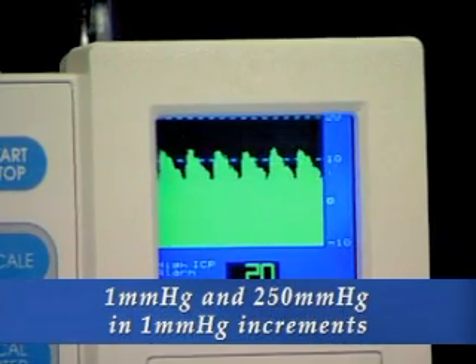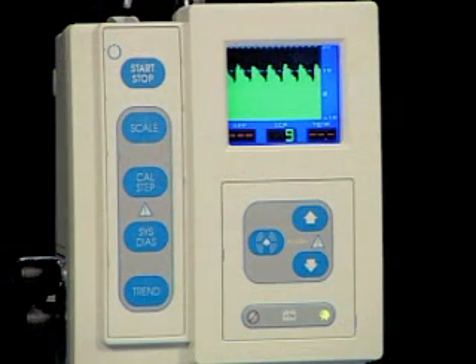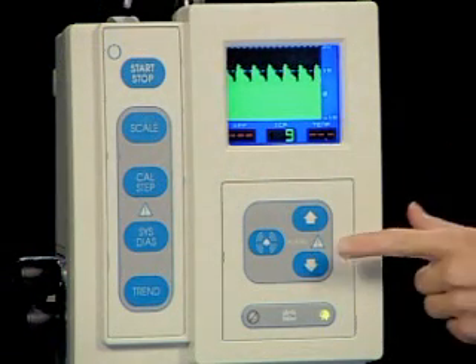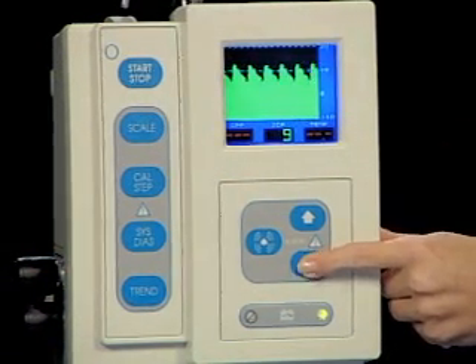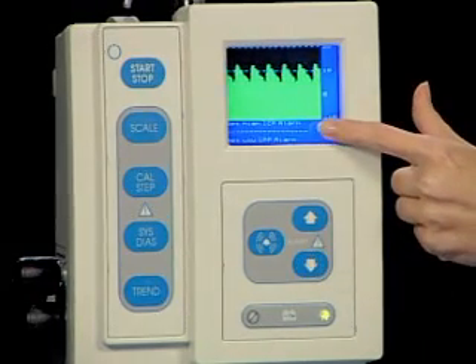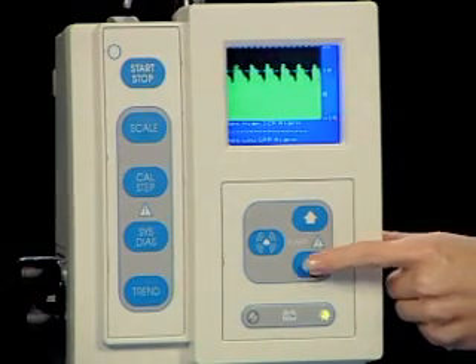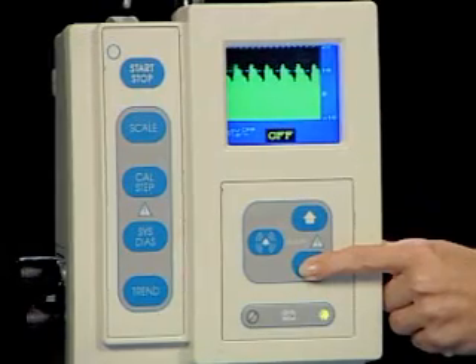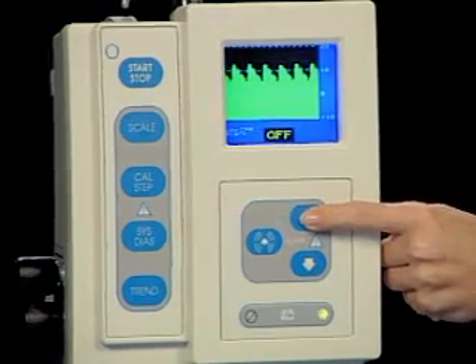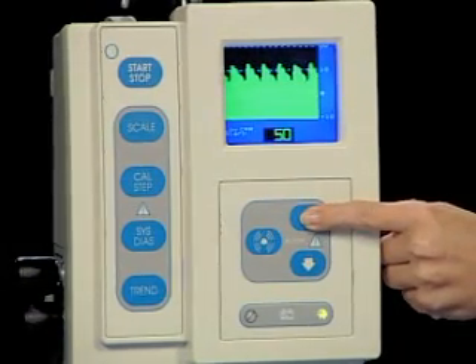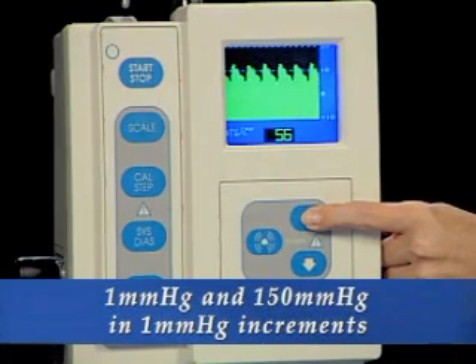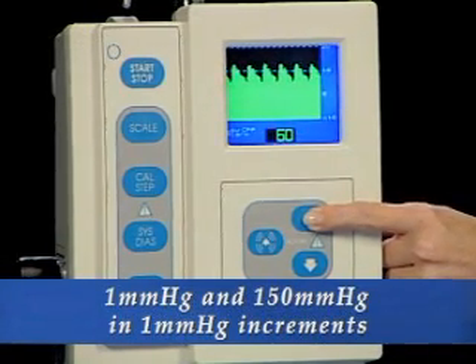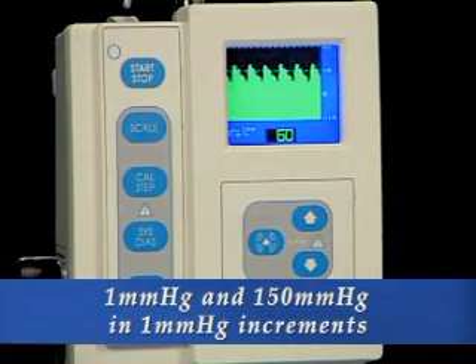To set the low CPP alarm, press the up or down arrow to view the Alarm Select screen. Next, press the down arrow to select the CPP screen. Use the arrows to scroll to set the desired value. The alarm value may be adjusted between 1 millimeter of mercury and 150 millimeters of mercury in 1 millimeter of mercury increments.